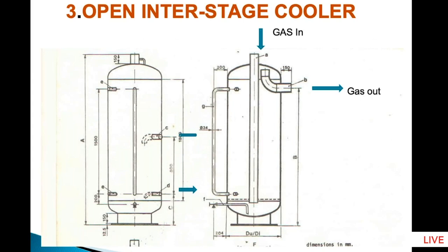You can see in the green line the gas inlet and the gas outlet, and the liquid connection. You can see both liquid inlet and liquid outlet on the left hand view. Here in this vessel the high stage gas and the low stage gas get mixed and come to the interstage pressure, and therefore there is no coil inside this cooler, and the interstage pressure is the most efficient pressure, and you get the best efficiency with this kind of cooler. There is a perforated plate also to distribute the gas uniformly. This is the internal construction.